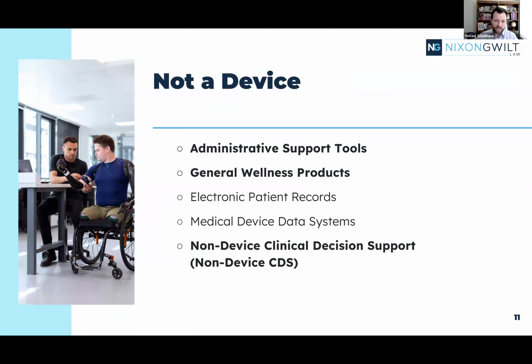So we're going to look at each of these three buckets and look at what the main red flags are and where you may fall with your different products. The first one is not a device. Within the 21st Century Cures Act, passed at the end of 2016, we have 5 groups of software functions that are excluded from the device definition. These are administrative support tools, general wellness products, electronic patient records, medical device data systems, and non-device clinical decision support. We want to highlight that non-device portion, and we'll come back to that in a second. Of these 5, the big 3 for AI-enabled products are administrative support tools, general wellness products, and that non-device CDS.